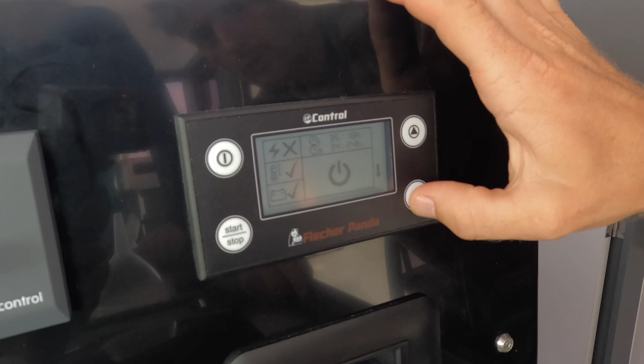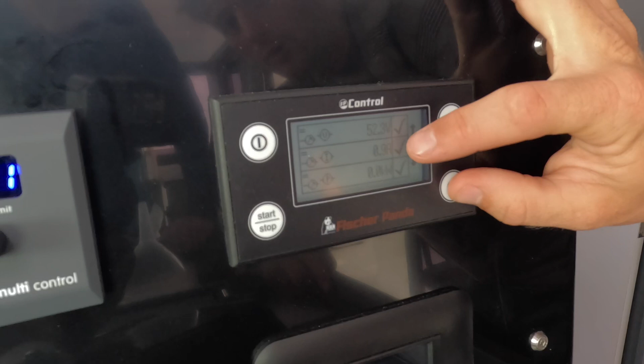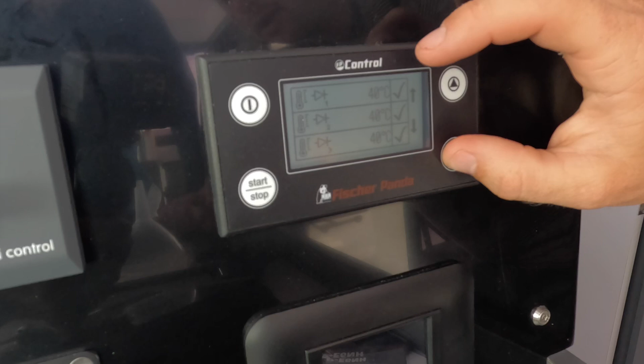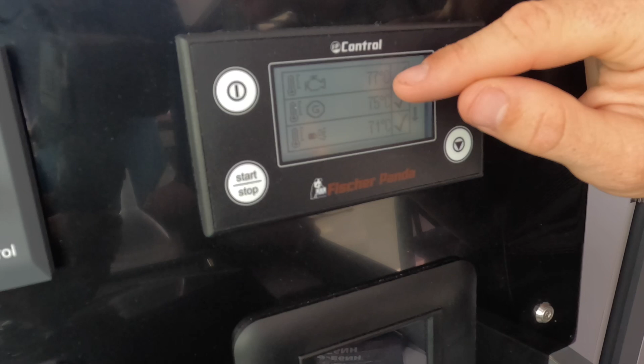Then if you go down you have more information: the tension of the 48 volt battery, the number of amps going into the battery, number of kilowatts, temperature of the three cables going out of the genset, the frequency, the RPM, and the 12 volt starting battery level. The temperature we were checking yesterday - you see it's still hot, it's been off for 1 hour now, so it's still a bit hot, but it's fine.